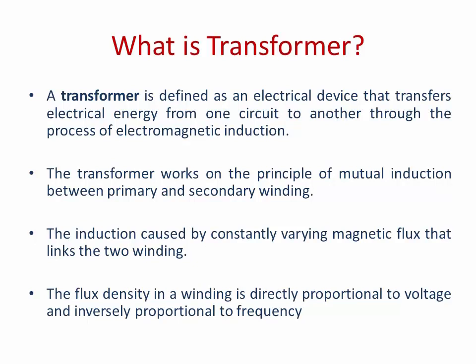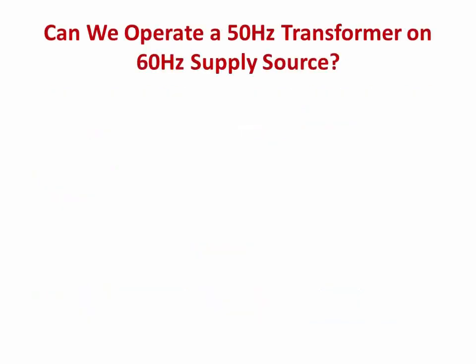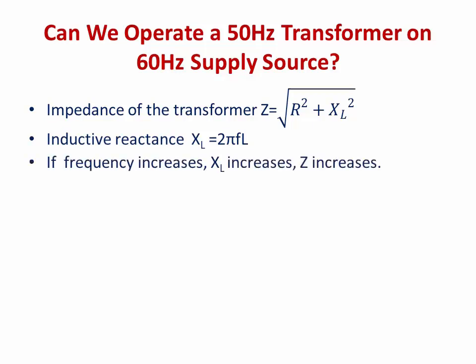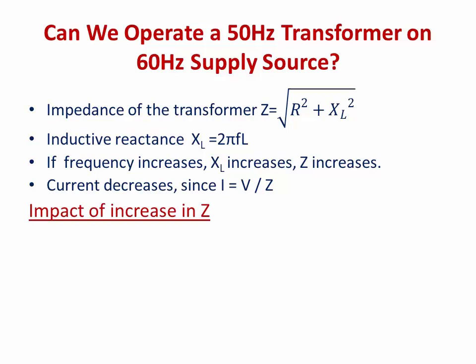The flux density in a winding is directly proportional to the voltage and inversely proportional to the frequency. Now, can we operate a 50 Hz transformer on a 60 Hz supply? The impedance of a transformer is based on resistance and inductive reactance XL. The inductive reactance XL depends on frequency — it is 2πfL. If frequency increases, inductive reactance increases, which increases the impedance of the transformer, thereby decreasing current flow since I = V/Z.